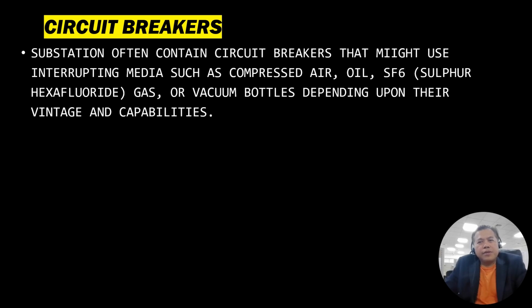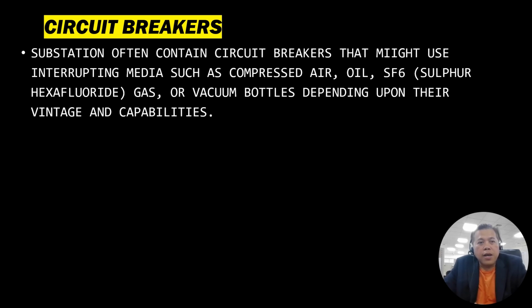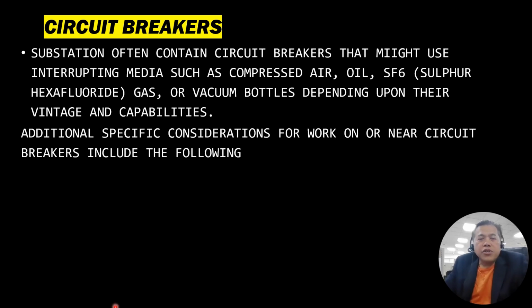So, circuit breaker. Guys, in substations, circuit breakers often use compressed air, oil, SF6, that is sulfur hexafluoride, or vacuum bottles for interrupting, depending upon their vintage and capabilities. So additional specific considerations for work on or near a circuit breaker include the following.